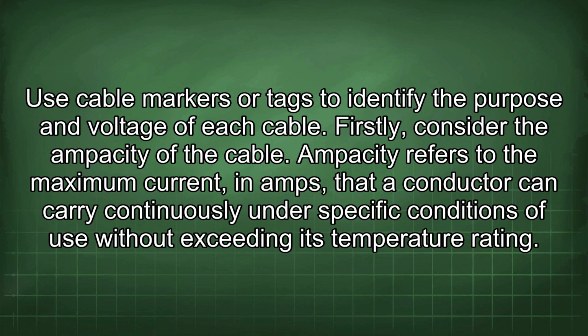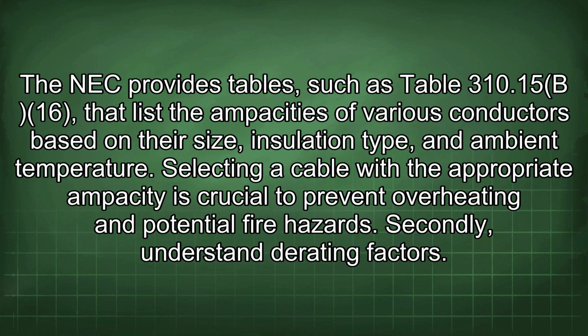Firstly, consider the ampacity of the cable. Ampacity refers to the maximum current in amps that a conductor can carry continuously under specific conditions of use without exceeding its temperature rating. The NEC provides tables, such as Table 310.15(B)(16), that list the ampacities of various conductors based on their size, insulation type, and ambient temperature. Selecting a cable with the appropriate ampacity is crucial to prevent overheating and potential fire hazards.